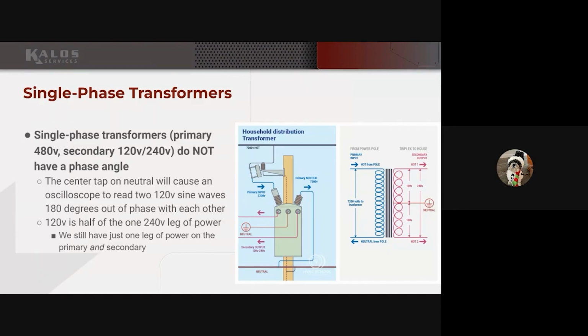Let's say that we have 240 volts at our point of service. So at our circuit breaker, we have 240 volts, but then we have a load of, say, 10 amps, and it's 300 feet away. Conductors are resistors, albeit they're really poor resistors. They're better conductors than they're resistors. That's why we call them conductors, but there is some resistance inherent in any conductor. And so the longer our circuits are, the more voltage that will be dropped across that load. That wire is in series with the load.